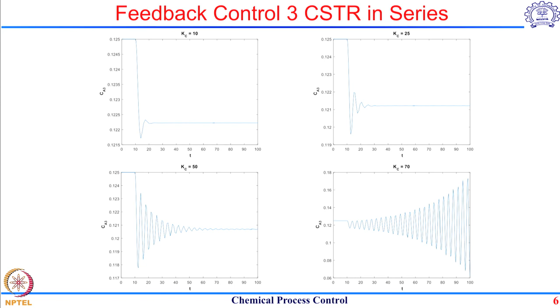If I increase this controller gain to, let us say, 25, the oscillations increase, and the offset also decreases. If we increase it to 50, you can see that the oscillations have increased tremendously, and all we are doing is increasing controller gain because we want to reduce the offset. And lastly, let us say I use a controller gain of 70. An interesting thing happens. You can see that the system no longer remains stable. All these oscillations, rather than decaying, are actually increasing, and the system is going to move towards instability.